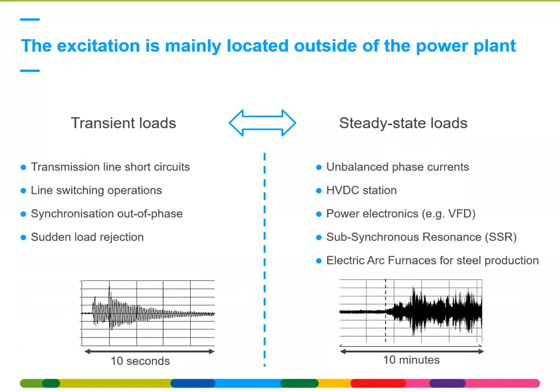Excitation, as explained, is mainly located outside of the power plant. You have a difference between transient loads and steady state loads. The transient loads, as you can see from the example below, are typically in the order of 10 seconds and are excited by short circuits, for instance, line switching operation, synchronization out of phase, or a sudden load rejection. These are all examples where you excite the shaft line in torsional vibrations, but as you can see below, typically within 10 seconds, the amplitudes are already below critical levels.